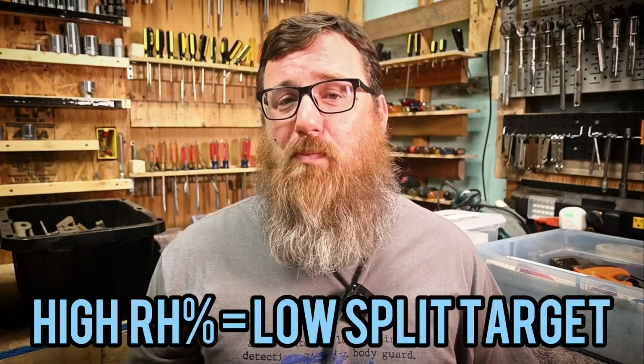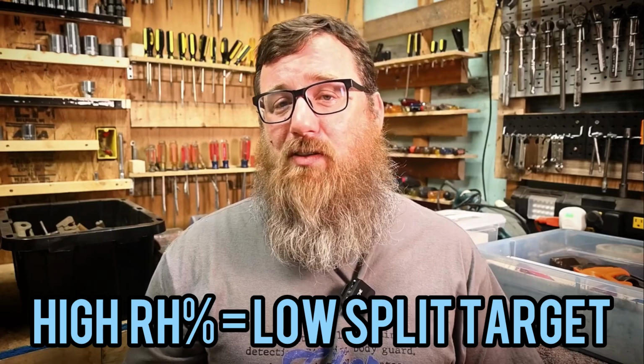Now, if you put your probes in there and your humidity is up to 80%, it's very, very humid in there. In fact, it's probably better to run the system for a while and try to dehumidify a little bit. But if you're all the way at 75, 80%, then your split's going to go way down because your system capacity has to address this latent load that's on the system. And it takes a lot of the energy out of the system instead of using it, for lack of a better explanation, to cool the actual temperature. So it's taking water out of the air and dehumidifying. Therefore, your split may be as low as 13 or 14 degrees, and that's normal.